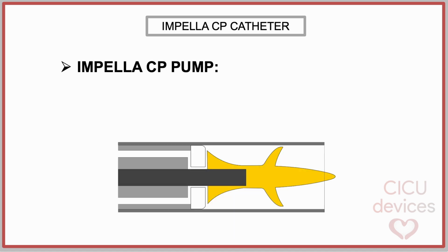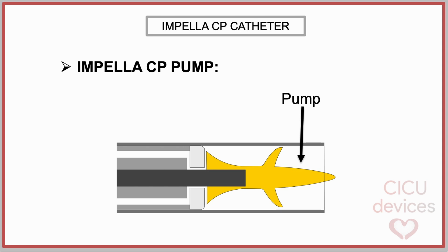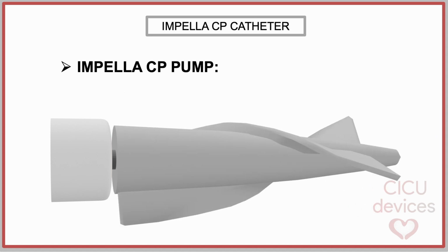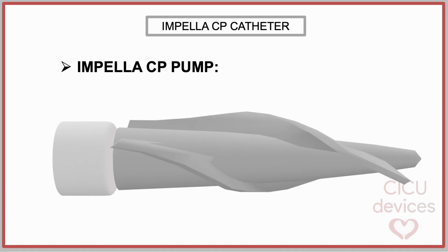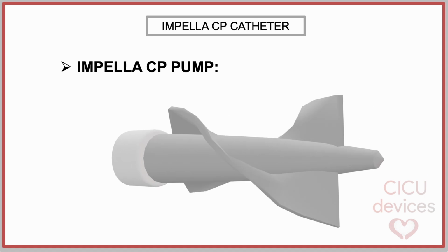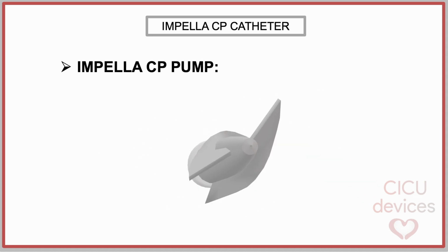This is a schematic drawing of a longitudinal section of the pump. It is connected to the motor through a shaft that is inserted into its longitudinal axis, leaving a gap of around 0.5 mm at its junction with the distal end of the motor housing. This gap is intended for the continuous flow of purge fluid to lubricate the friction area, prevent excessive temperature increase, and avoid thrombus formation in this region. The impeller is driven by the electric motor transmitted by the shaft with a counterclockwise rotation when viewed from its most distal part, as we can see in this animation.